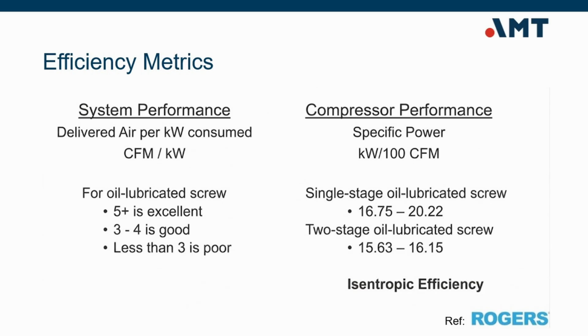This slide introduces efficiency metrics. Efficiency is measured by much more than pressure alone. Pressure matters, but it doesn't tell the whole story. To truly understand performance, we look at several key metrics: pressure stability, flow, energy use in kilowatts, compressor loading behavior, and leak rate. But ultimately, all of these roll up into one core question: how much energy does it take to produce useful compressed air?